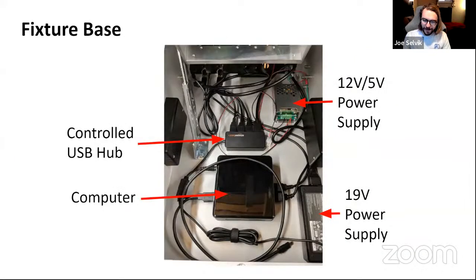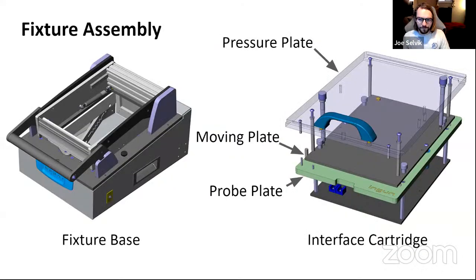If you go back one more slide, we'll walk through the different layers in there. At the top you have the pressure plate, then a moving plate, and then a probe plate. We have some images later on this, but basically that pressure plate comes down and is vertically actuated, so it directly pushes that device down flat against that moving plate. This helps prevent warping in that device under test.